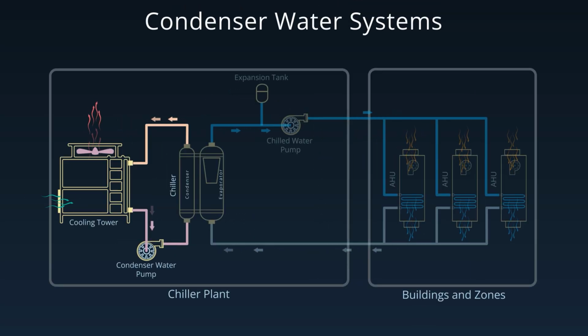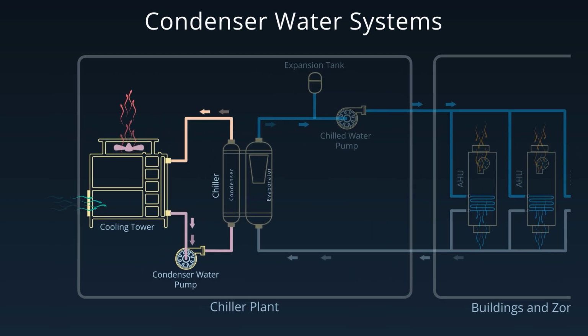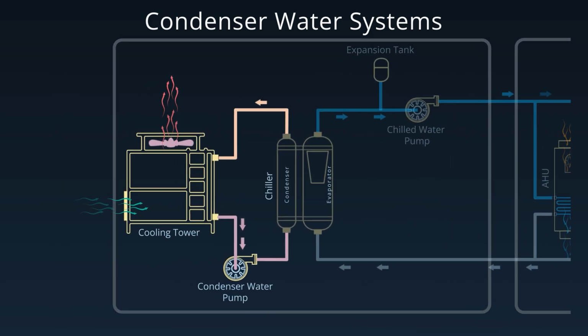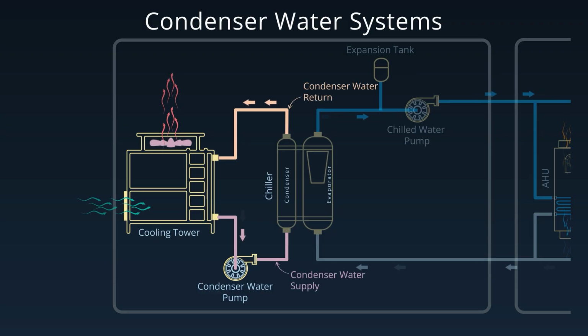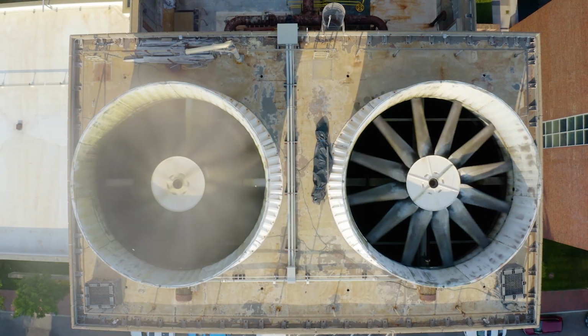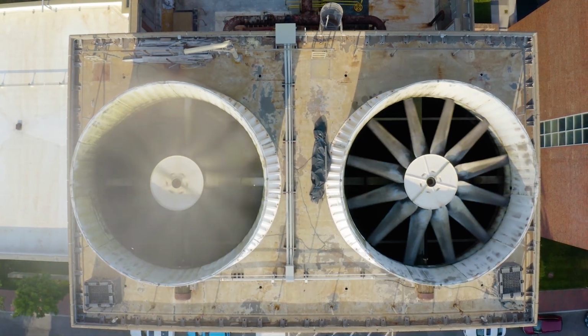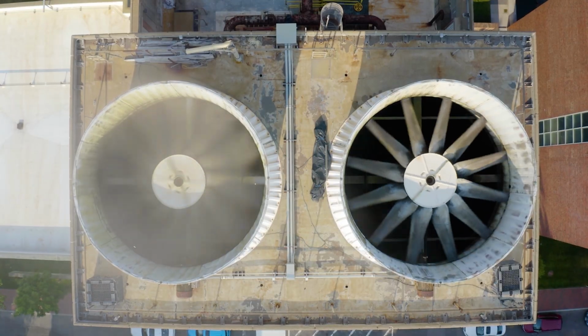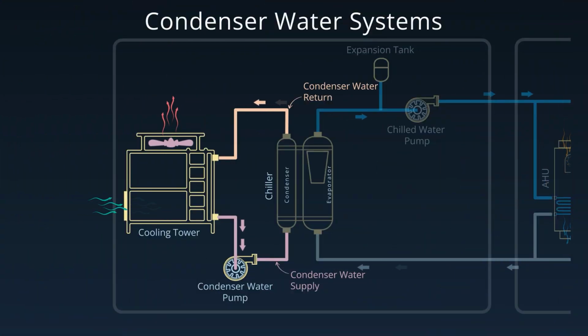A condenser water system is most commonly a part of a water-cooled chiller plant. When a chiller removes heat from chilled water, the heat has to go somewhere, and it's rejected into the condenser water system. The condenser water absorbs the heat in the chiller's condenser, then flows to a cooling tower. The cooling tower releases that heat into the atmosphere, usually through evaporation. After cooling down, the water cycles back to the chiller condenser.